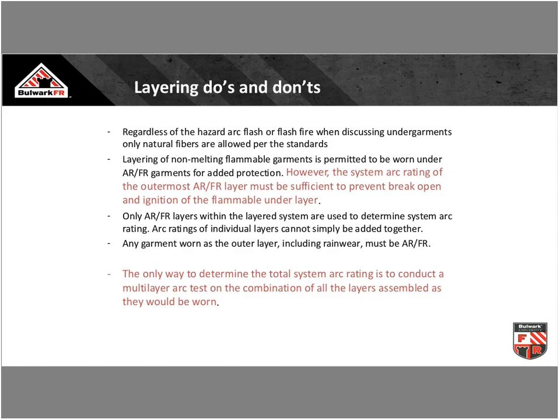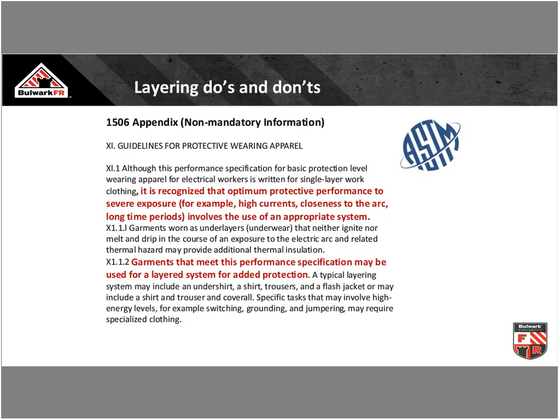In that reasonable estimate of incident energy, you need to have not just a little bit more, but probably a significant amount more so that it does not break open. Or you need to know where the break-open point is so you're comfortable you're not exposing an ignitable underlayer to any leftover energy. Only arc-rated FR layers within the layer system are used to determine that system's arc rating. Arc ratings of individual layers cannot simply be added together. That's a long-winded way of saying we have to test them as they're going to be worn to know what that system is, and ultimately you have to know that if you're incorporating it for higher incident energies.